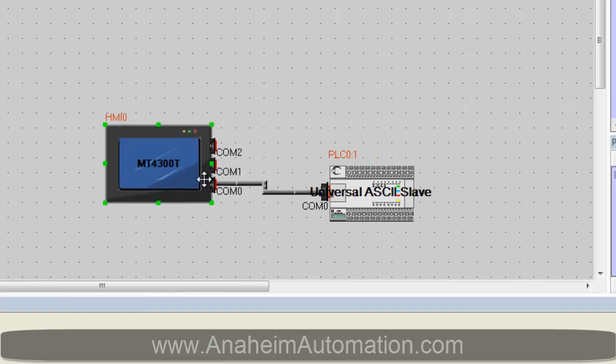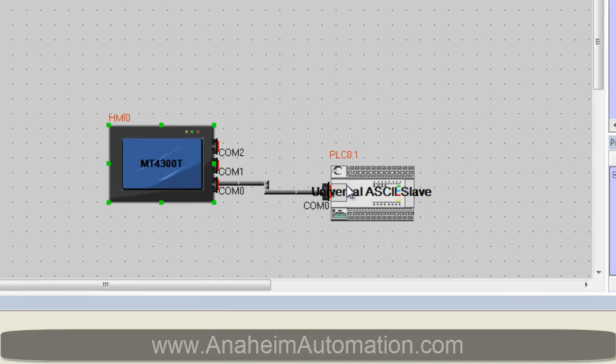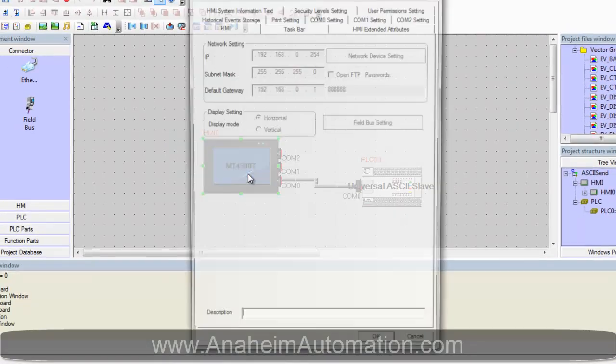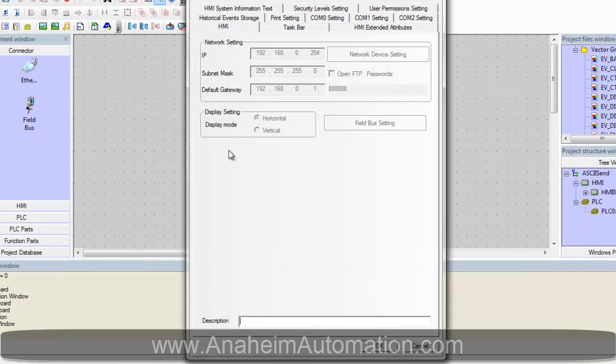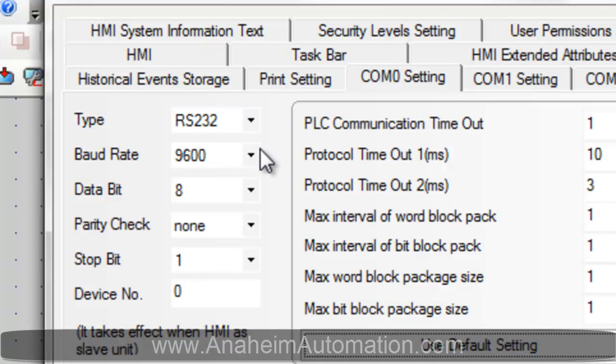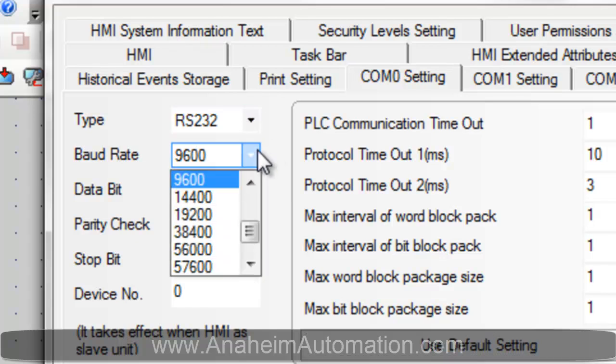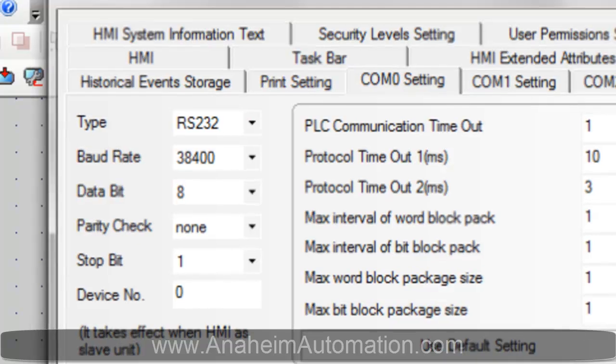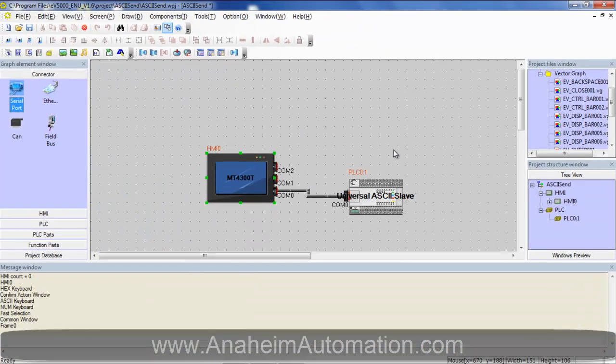We also have to verify that both the HMI and the PCL601 baud rates are in sync. The PCL601 only accepts a baud rate of 38400. So we must verify that the HMI's COM0 settings are both an RS232 cable and is set to 38400. Once we have done that select OK.